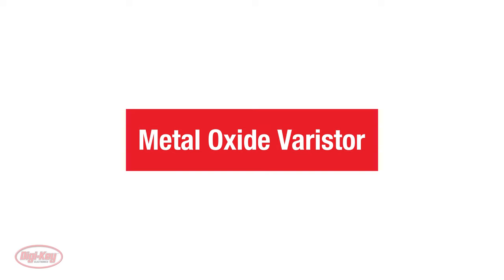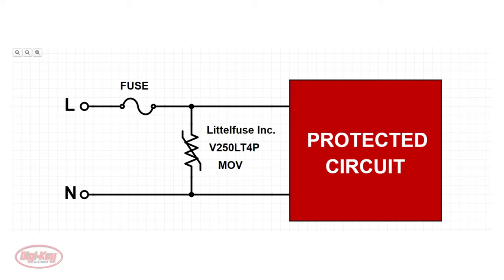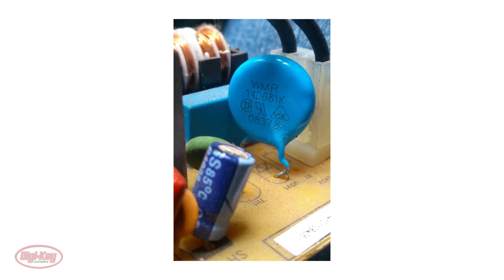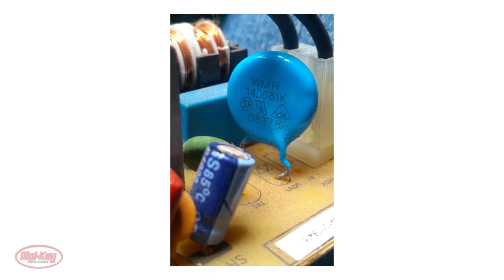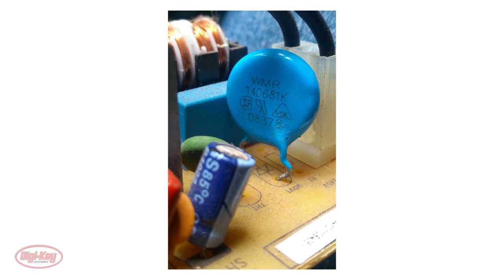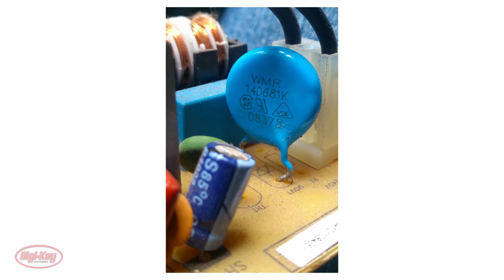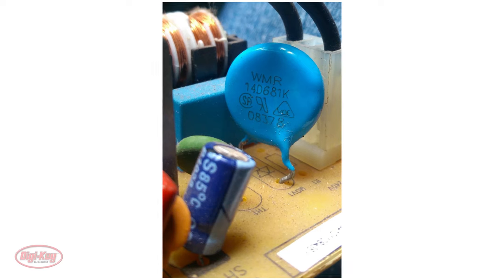Another device used in circuits to suppress transients is a metal oxide varistor, or MOV. It behaves like a variable resistor that has very high resistance under normal situations, but suddenly drops its resistance to almost zero ohms during transients. Much like with TVS diodes, metal oxide varistors are also connected in parallel to the electronic circuit to be protected. Usually, metal oxide varistors are designed to be operated continuously across AC power lines, just like the V250LT4P. If transients are within the limits of the MOV used, it can be used after multiple surges.